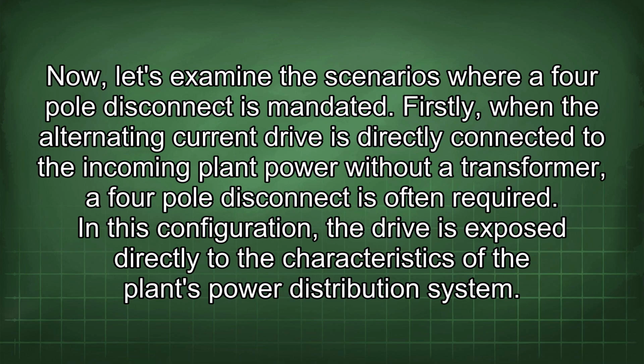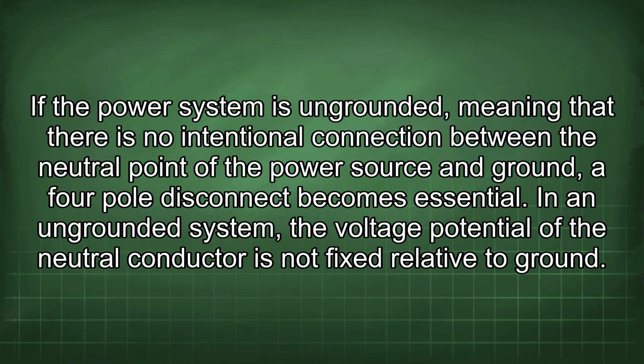Firstly, when the alternating current drive is directly connected to the incoming plant power without a transformer, a 4-pole disconnect is often required. In this configuration, the drive is exposed directly to the characteristics of the plant's power distribution system. If the power system is ungrounded, meaning that there is no intentional connection between the neutral point of the power source and ground, a 4-pole disconnect becomes essential.